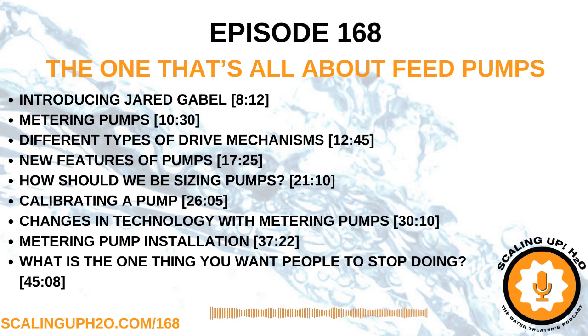As far as what goes into it, it really depends on the manufacturer's process. One of the things that we do in our pumps is we have a calibration setting. It goes through a series of strokes and counts them, up to maybe 100 or 200 strokes, depending on the model. Once that's done, you read the drawdown level of your calibration column physically. The pump will say, I think you just displaced 100 milliliters. Then you read your calibration column and it says, actually, I've displaced 120 milliliters. So then we just input that value into the dosing pump and select OK, and then it's calibrated.